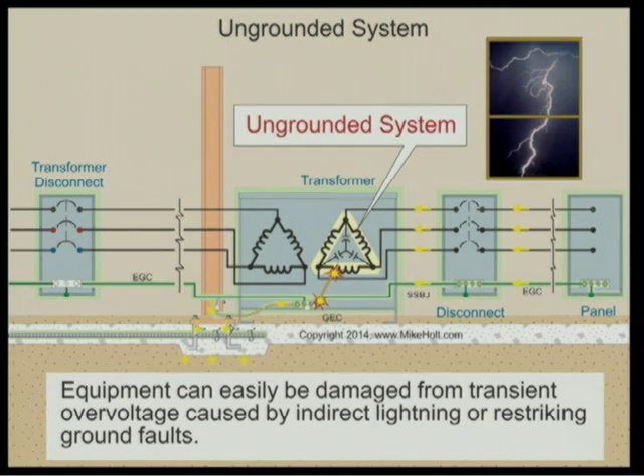Well, then there's no grounding of an ungrounded system. We're talking about system grounding. In system grounding, you could have an ungrounded system — that's a type of system grounding. But what are the problems with ungrounded systems? There's a problem with an ungrounded system: equipment can easily be damaged from transient overvoltages caused by indirect lightning and re-striking ground faults. If you heard what I just said, you should have no clue what I'm talking about. But take a look at the next slide.